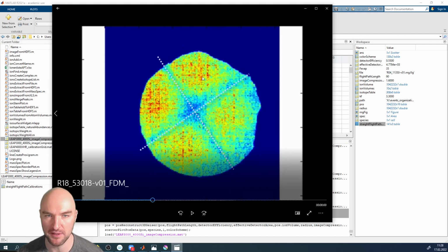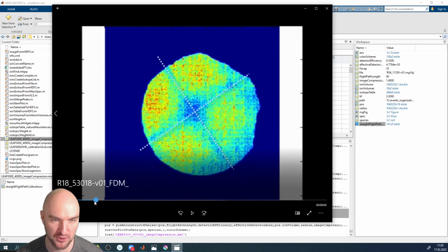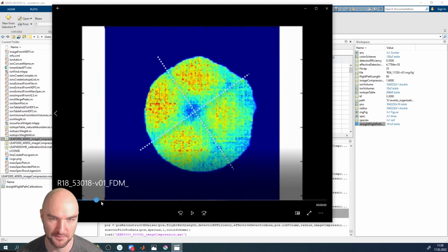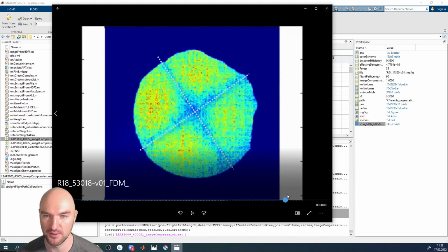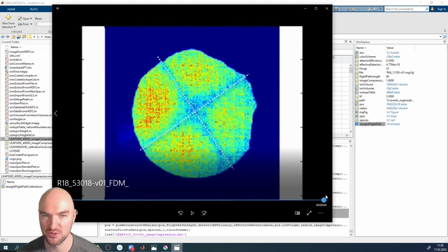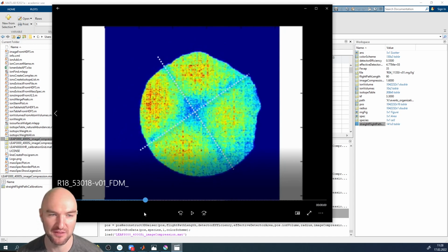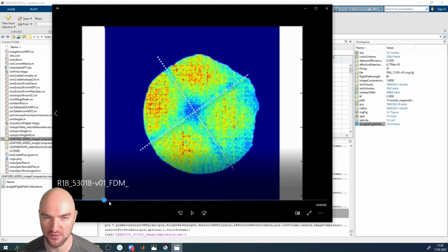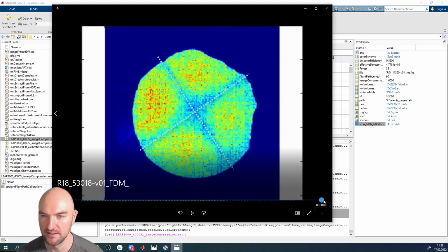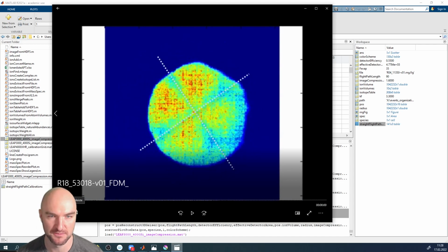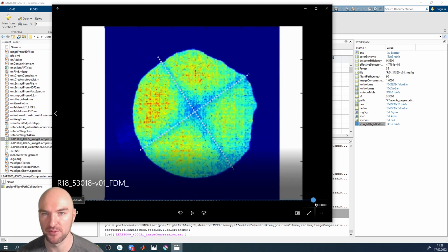All you need to do is maybe take one of those pre-sharpened posts, underfill a detector, and then just let it run, well, until it stops. You don't even need pulsing. You can just switch off pulsing your laser, no voltage pulsing.